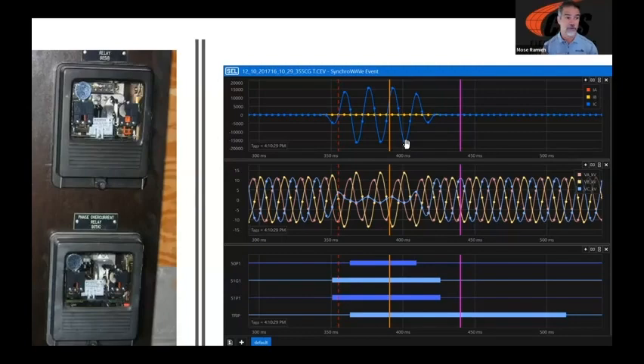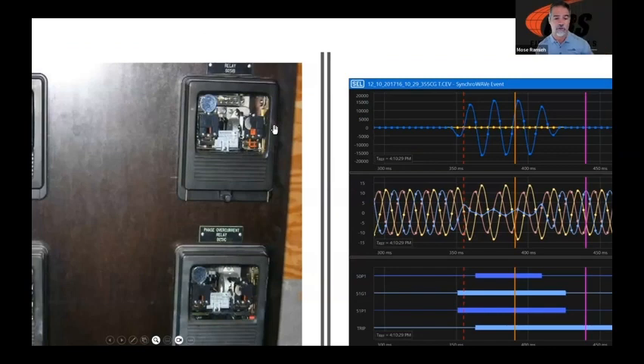And really quick, once again, back in the day, we got an orange target and you get a phone call and says, hey, I was sitting at the house on a Saturday, getting ready to maybe crack open the first cold beer after mowing the lawn, and get a call from a client that says, hey, I had a breaker operation and I wondered if it was safe to turn it back on. I said, well, what kind of trip was it? A time or instantaneous trip? And they said instantaneous. And I said, no, you don't want to turn that back on.